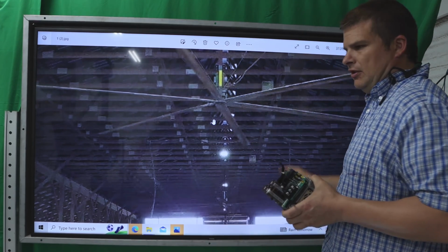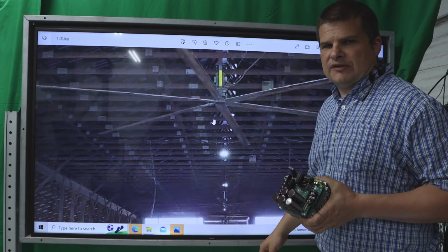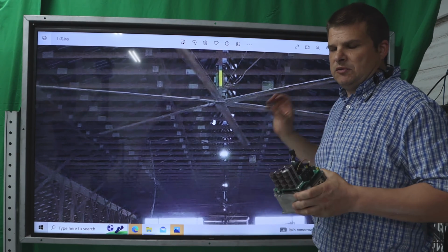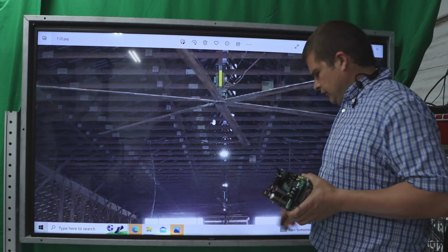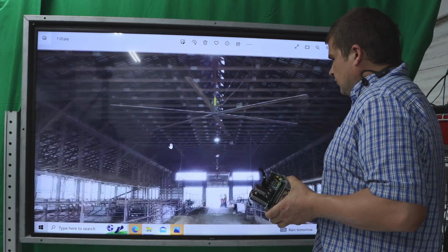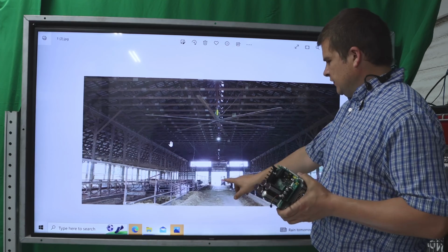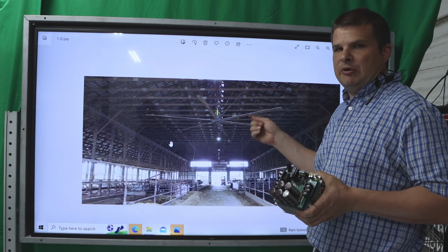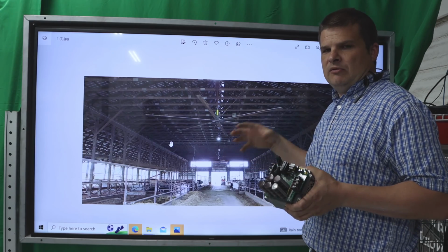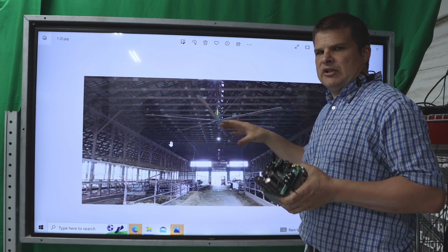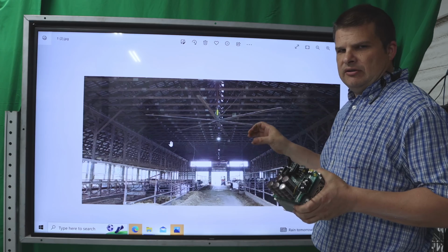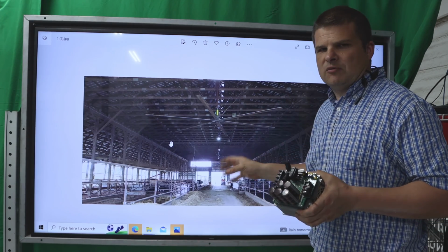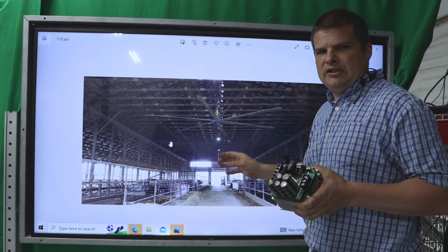So for this particular installation, it ended up costing around $1,000 to go out and replace two VFDs. It was actually pretty close, and we spent several hours figuring out exactly what's what. You can see the lift right there. For this particular job, we went out and none were running, but we figured out the two shorted out ones were shorting the whole system out, and we replaced two variable speed drives and got the whole system running. Till we left, everything was running.